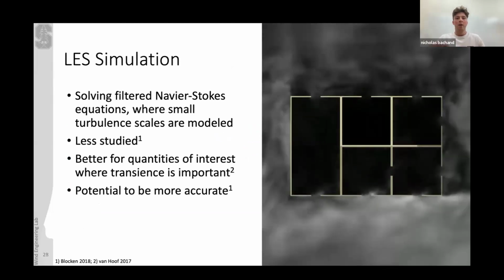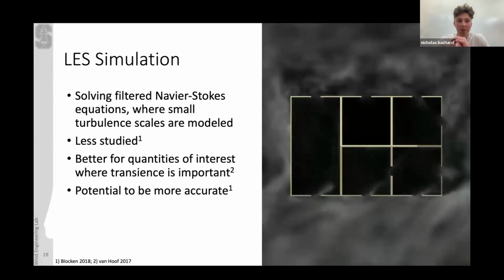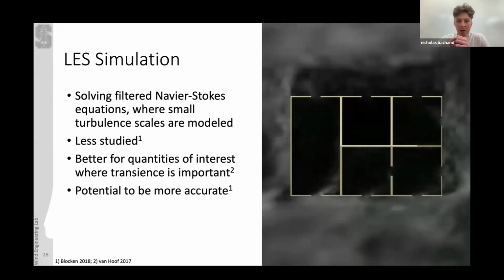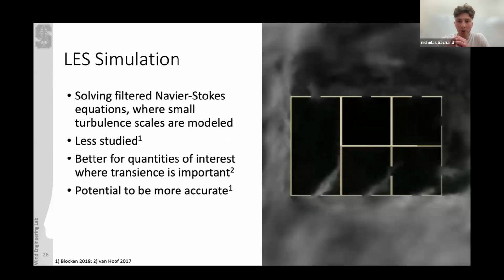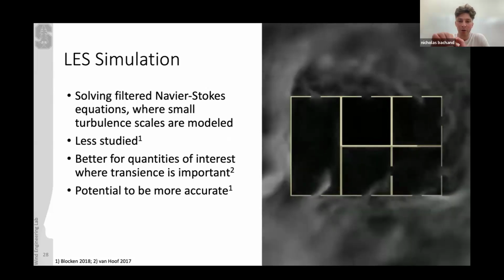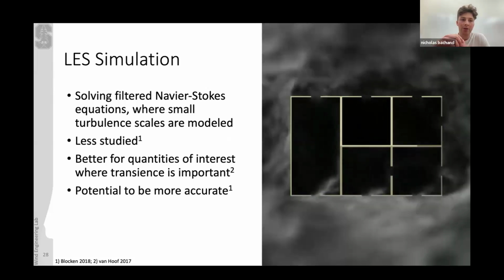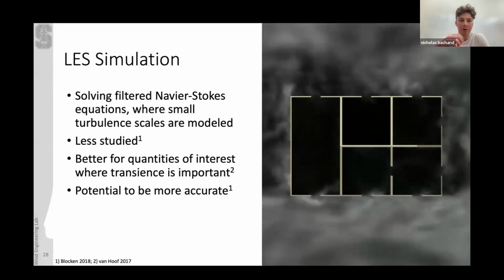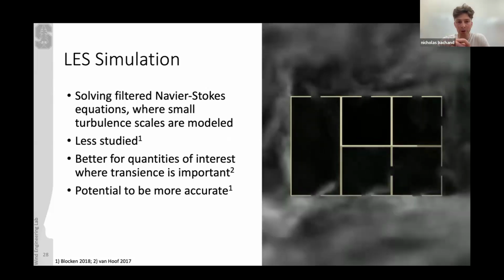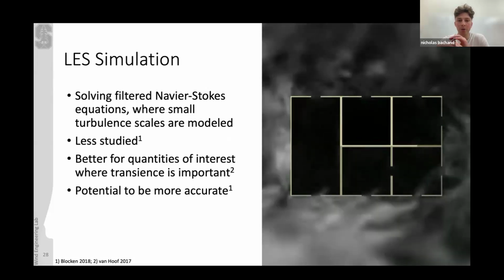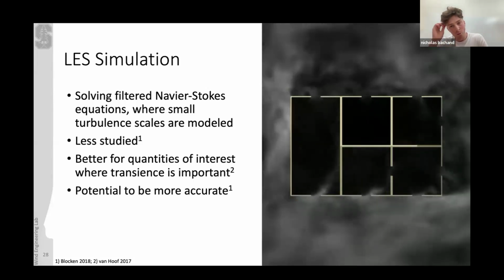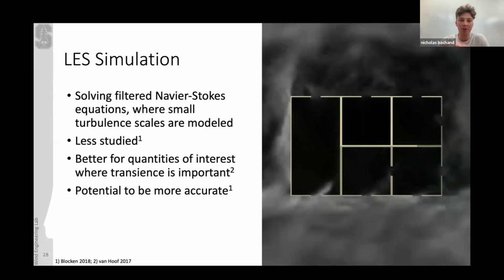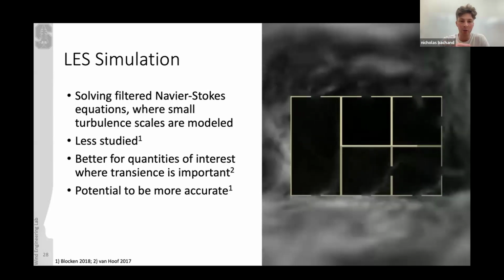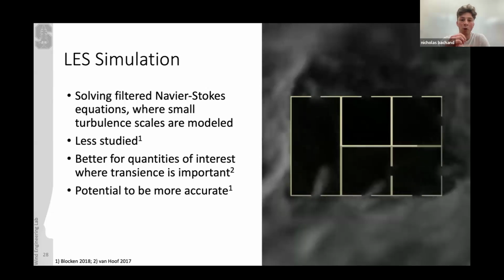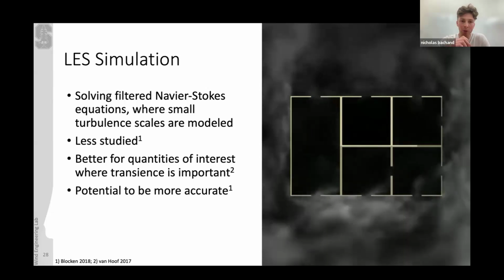I'm going to step back a bit and give some context on LES simulation. On the right is the flow field through one of the rooms during this natural ventilation. What the LES does is filter the Navier-Stokes equations, so small turbulence scales are modeled and larger turbulence scales are simulated directly. These types of simulations are less studied and are not the industry standard, which generally uses more turbulence modeling.